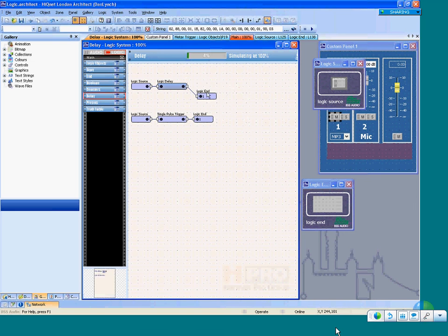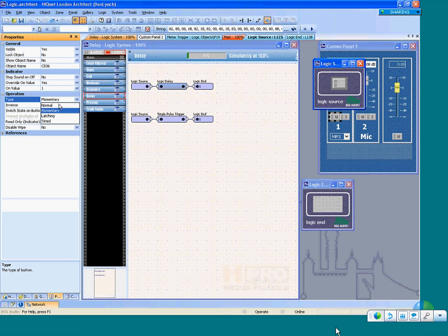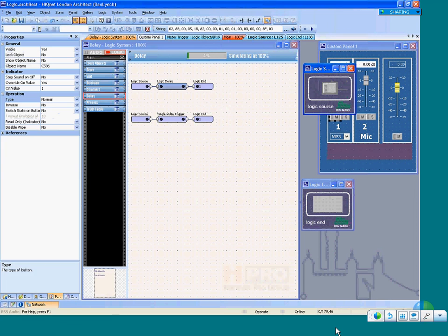It's also a great thing to use on fire system relays, fire system inputs. The worst thing in the world is when that fire system resets itself. Oh man, every time they reboot the fire system, it loses connection for a split second and triggers who knows what kind of chaos in your audio system, whatever you programmed in there. Okay? Normally, a fire system is going to be a normally closed contact. So it's going to look like that most of the time.